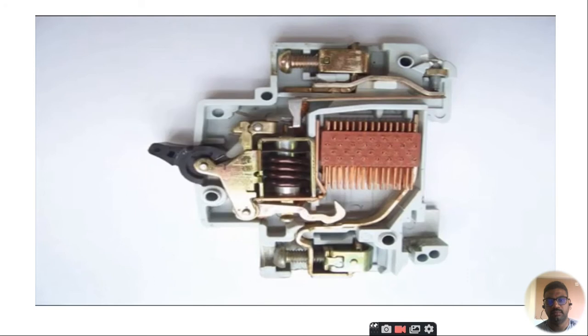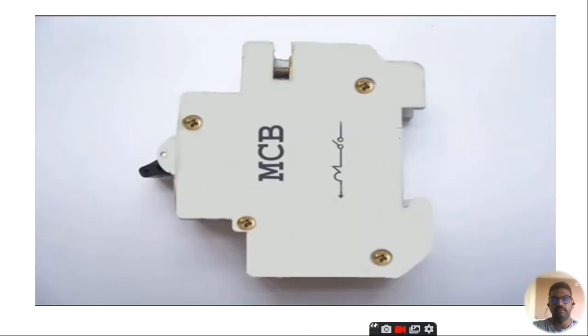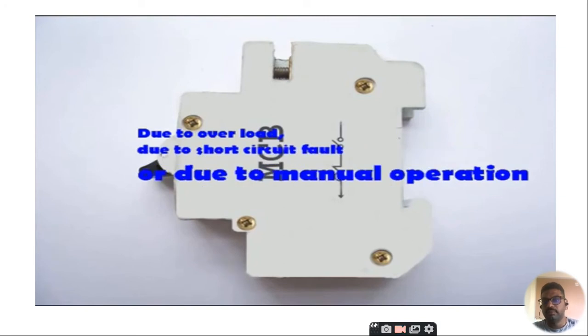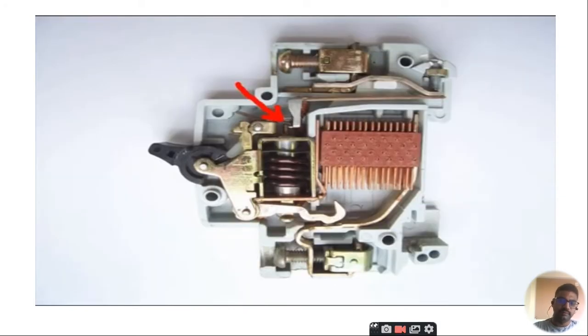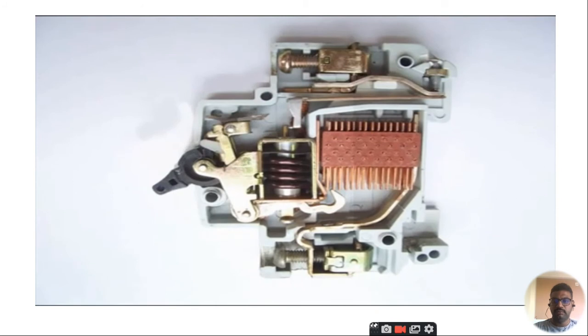When the MCB is required to be switched off manually, the operating lever is operated by hand. When we do so, the same latch point is displaced, and as a result, moving contact is separated from fixed contact and the MCB becomes off position. So whatever the operating mechanism - due to overload, short circuit fault, or manual operation - the same latch point is displaced and the spring is released, which is ultimately responsible for movement of the moving contact.